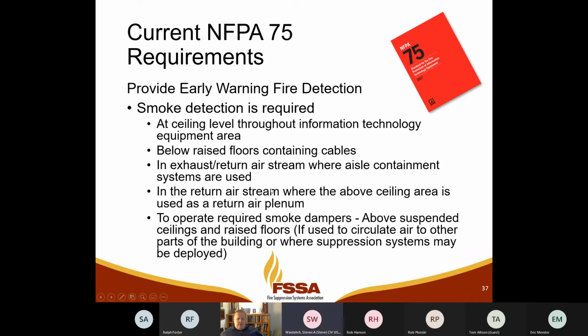So Lee, when it says containing cables, right? Yes. It doesn't matter if it's plenum listed or non-plenum listed, correct? Correct. It does not. That plenum rating comes into play whether or not you need suppression under the raised floor. Like gaseous suppression, when you're talking about that, in NFPA 75 it always says you need to have suppression when these things are there, when you're following the prescriptive requirements out of it.